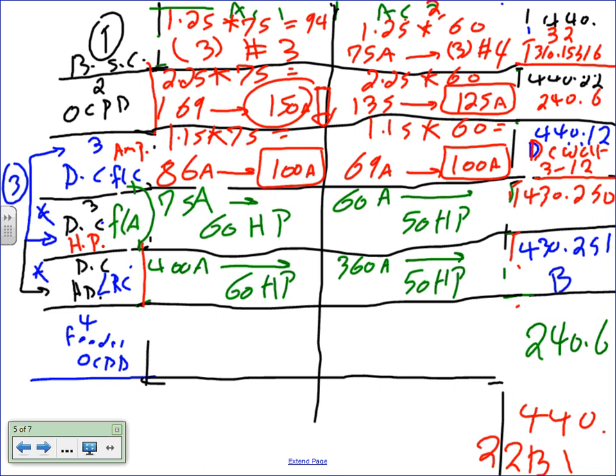So when you go to the electrical supplier and order your disconnect for this equipment, you're going to say, I need a 3-phase, 100 amp, 480 disconnect rated for 60 horsepower, and the other one rated for 50. Now, they might not make 100 amp at 50 horsepower. They might jump immediately from 100 to 60. So can I use a 100 amp, 60 horsepower rated disconnect for this? Yeah, no problem. It's just overrated a little bit. So to standardize, you can order this one, which is 100 amp, 60 horsepower, disconnect 480 for both of them. Because this is 50, I am asking for a minimum of 50, but I add 60, so it's stronger.